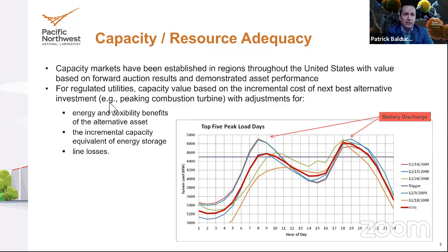Effectively, they drive down the price. So energy storage systems can sometimes be a victim of their own success here in terms of their effectiveness in providing capacity and, of course, frequency regulation. And it's important to account for that because if you're bidding into a market expecting the current market rates, remember the system may last for 10 to 20 years. Those rates may not be realized in years 3 and 4 and all the other out years.